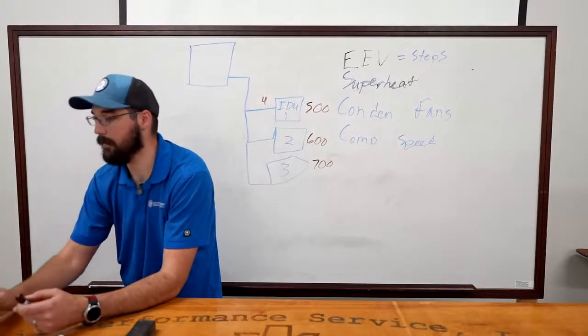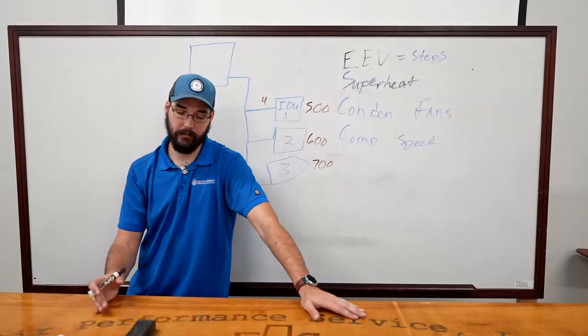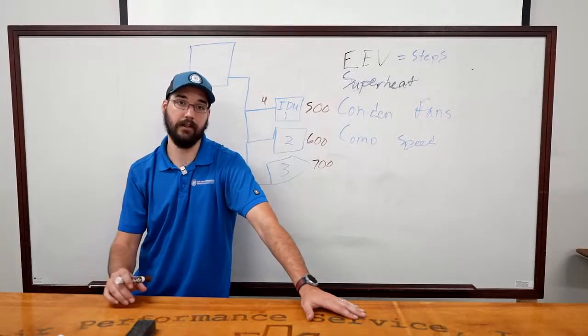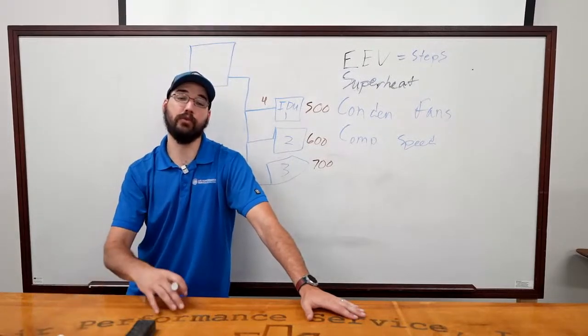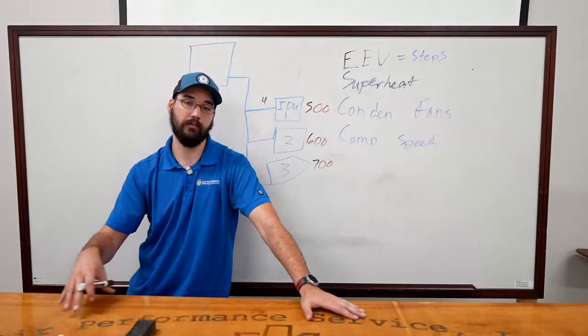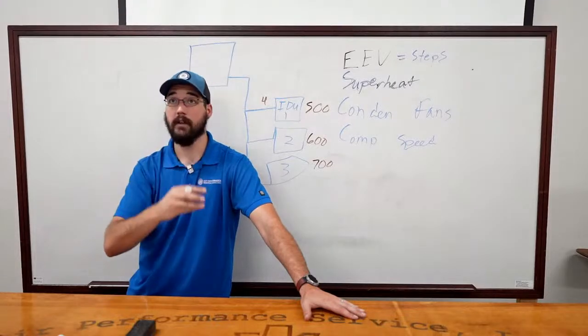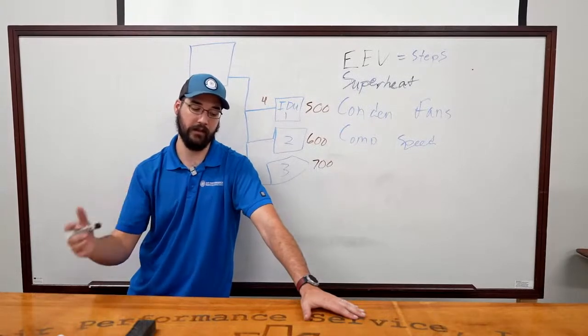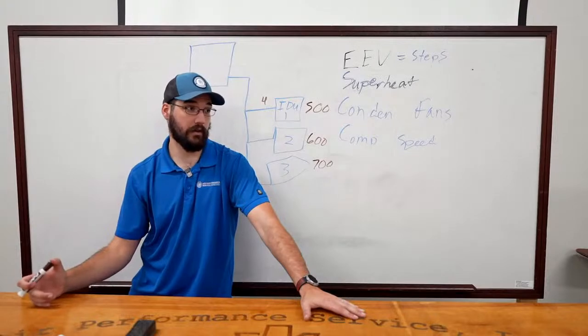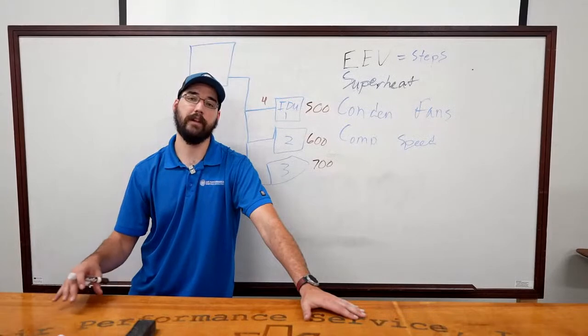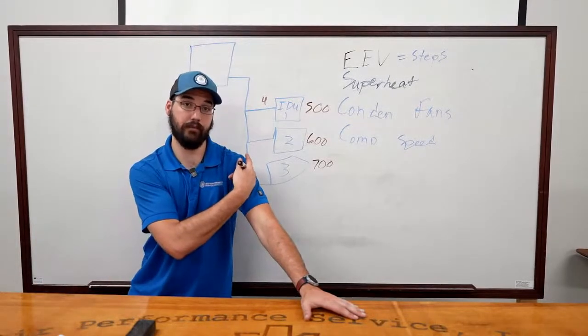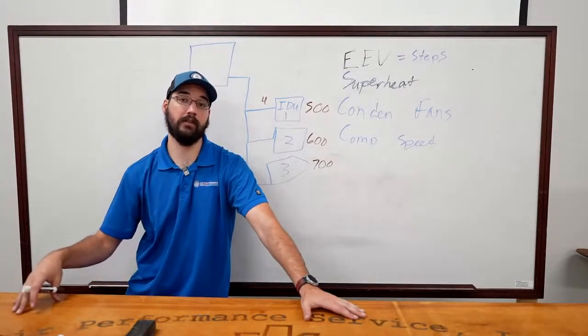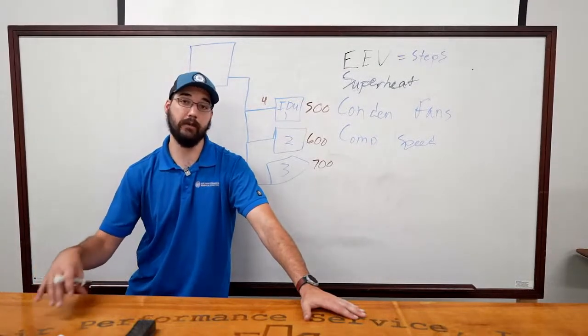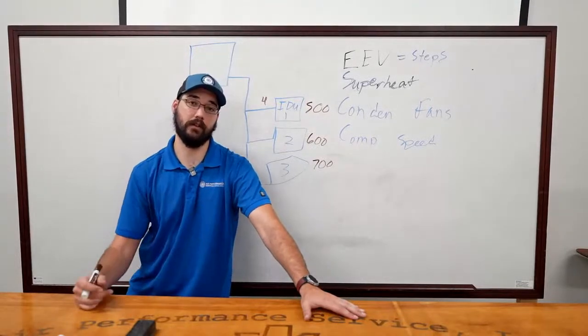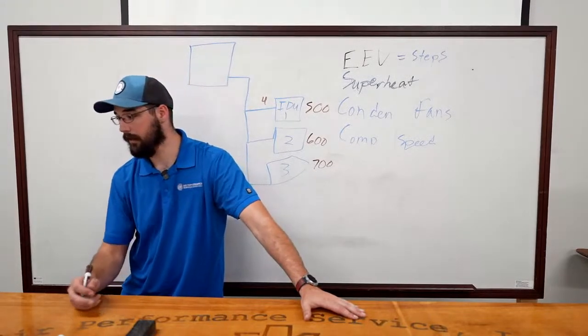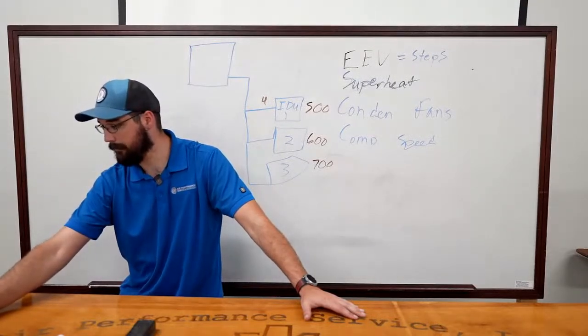It's been interesting. I've talked quite a bit recently about how the VRVs are really pushing on the commercial market and really challenging what used to be either a large RTU or a chilled water system. The VRVs are a cheaper option, and so they've won a lot of those bids. There are quite a few people saying that they're starting to go back the other way, I think especially in Europe. They've had so many years of so many problems, and they have failures, and it's gotten so expensive to operate these things that their budgets were cheaper with a chilled water system and a chiller than trying to keep these things online long term. The longevity wasn't there. It's a pretty interesting conversation to see happening, kind of watch from the background.